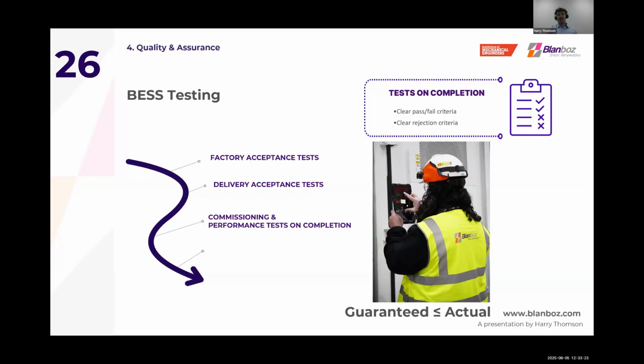Once the equipment has been installed at site, comprehensive commissioning tests are conducted. These tests include active and reactive power testing, frequency response tests, and grid compliance and grid services tests. This is to evidence that the project is compliant with the grid code and the grid connection agreement, as well as that it can deliver the services it was procured to do. At a similar time in the project, you also have performance tests on completion, and these are used to verify that the performance is as expected, that it meets the guaranteed or higher values for energy capacity and round-trip efficiency.